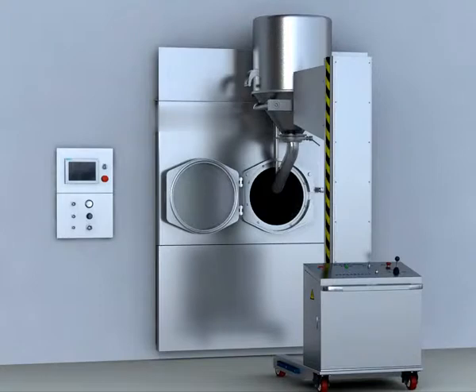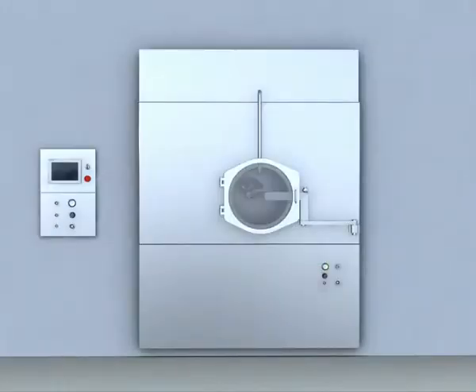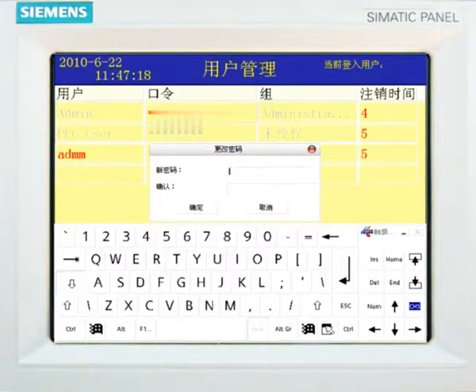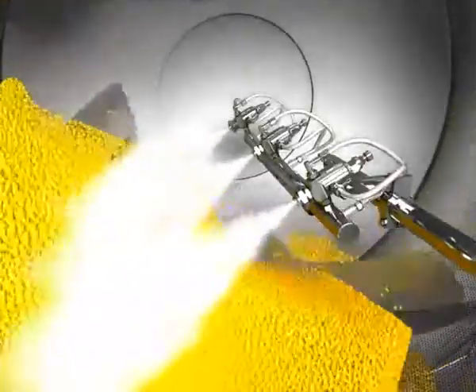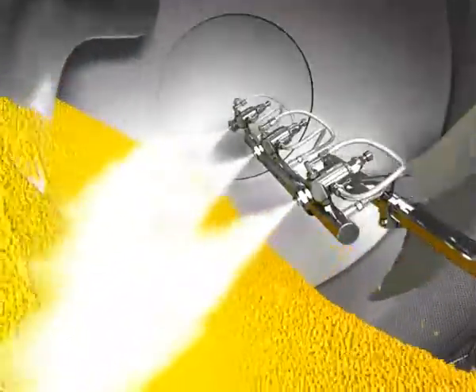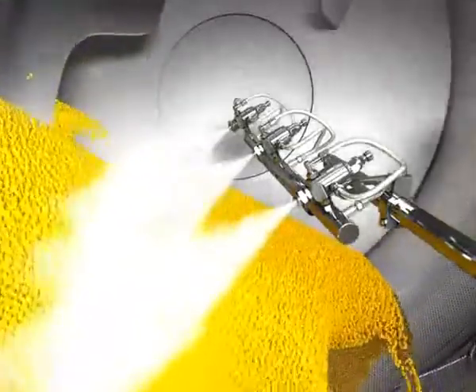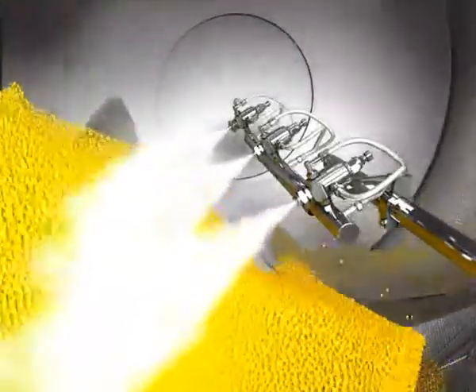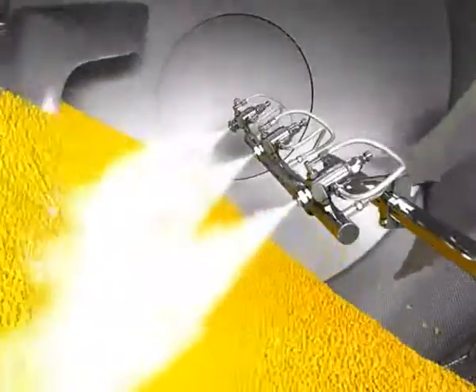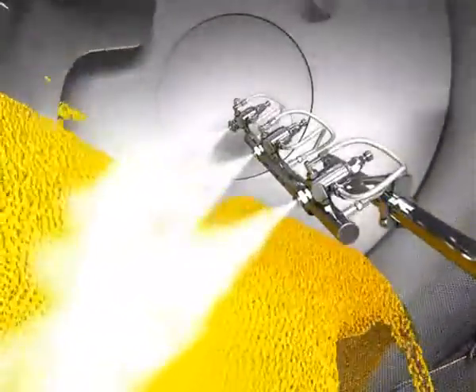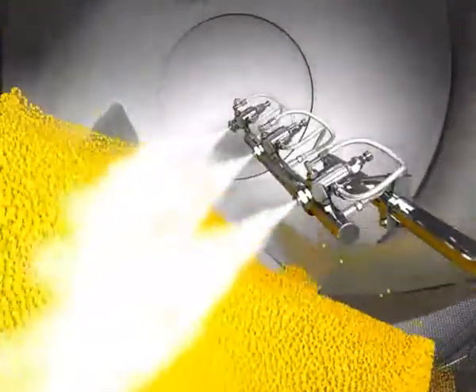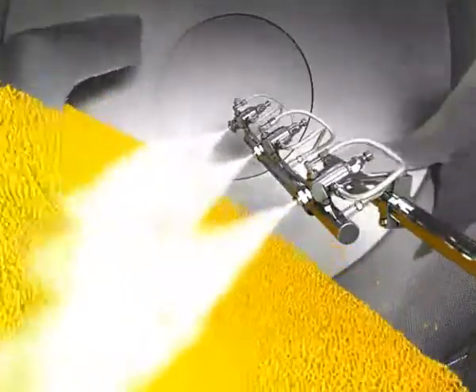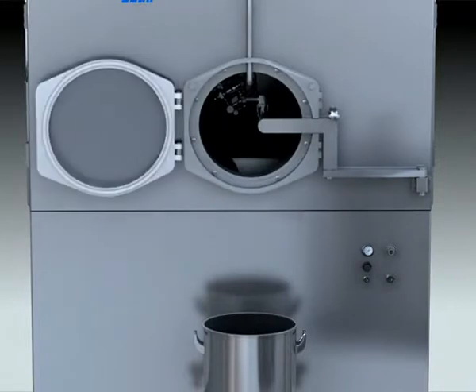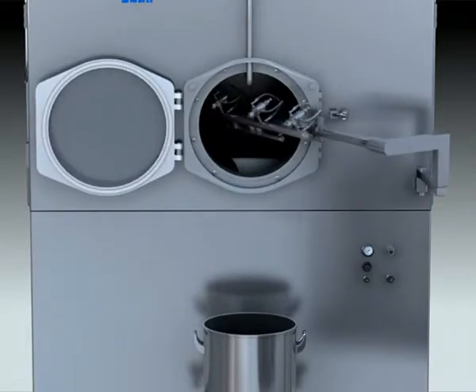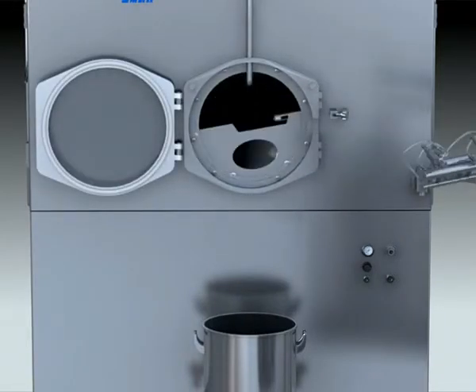With tablets moving continuously in the rotary drum, a coating film is gradually formed on the tablet surface. After coating is finished, install the automatic discharging device. Discharge finished tablets from the drum and finish the process. After the coating process, switch on the WIP system. Wash the coater with tap water, washing detergent and pure water. After which, turn on the drain valve. Start pipe reserve blow and finish the washing process.